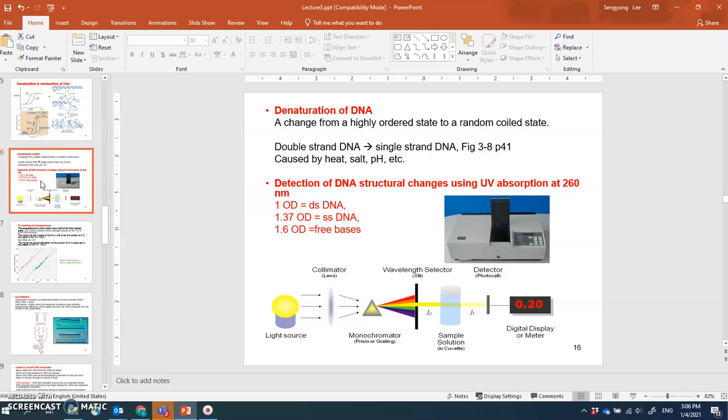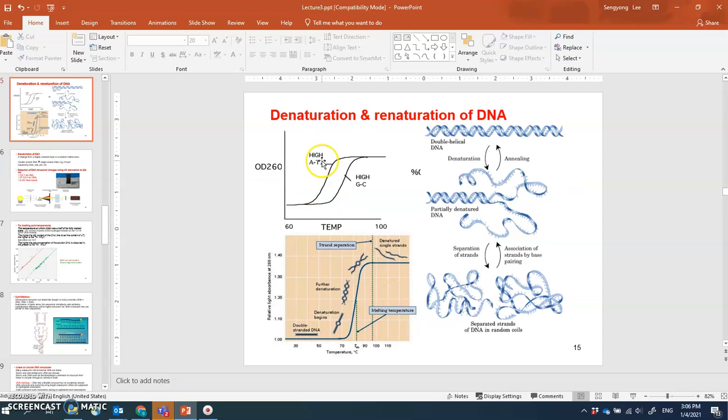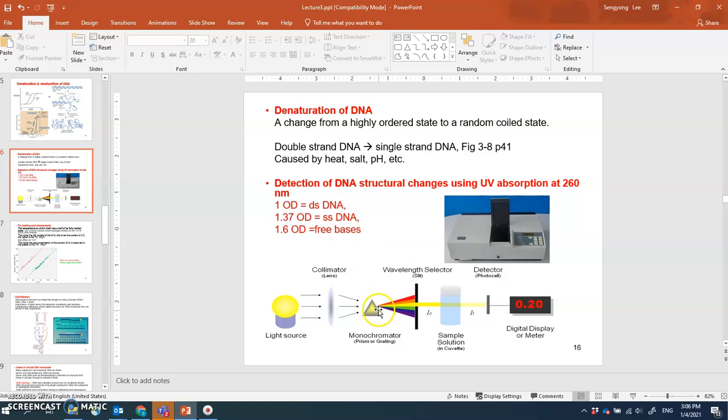So like I just told you, the conversion of DNA conformation can be measured using this machine called a spectrophotometer. Inside of this box, there's a light, maybe tungsten with deuterium light, that generates UV light. You can select different light wavelengths using this prism, and then selected light in the 260 nanometer range can be shined through your DNA sample that is dissolved in water.